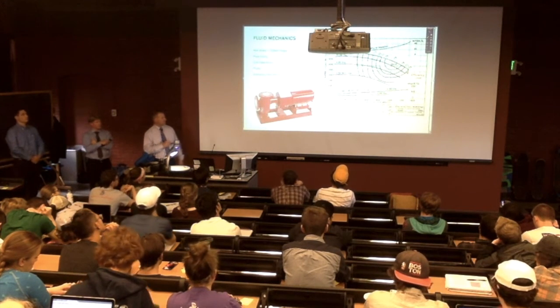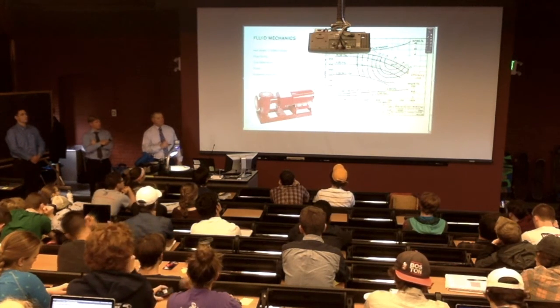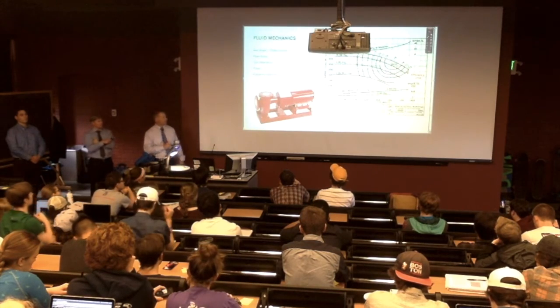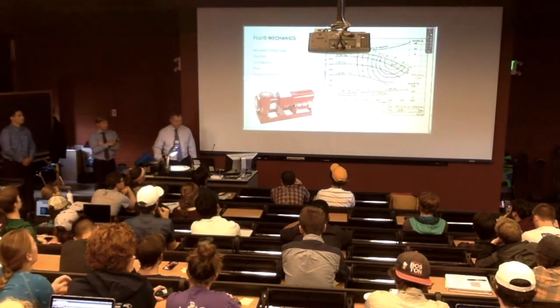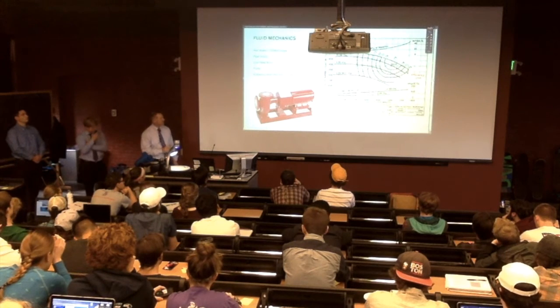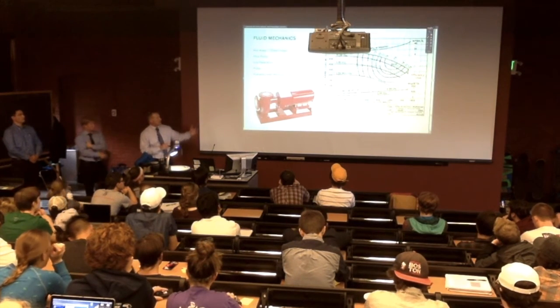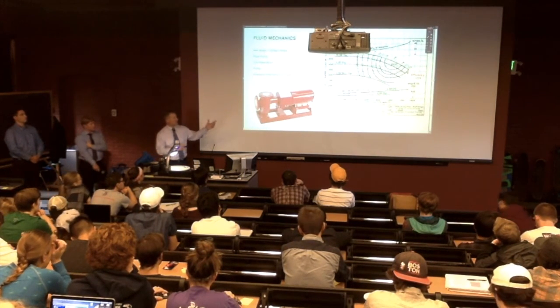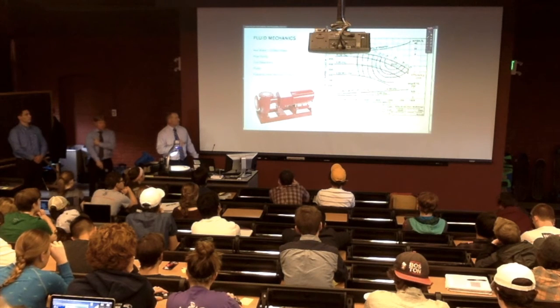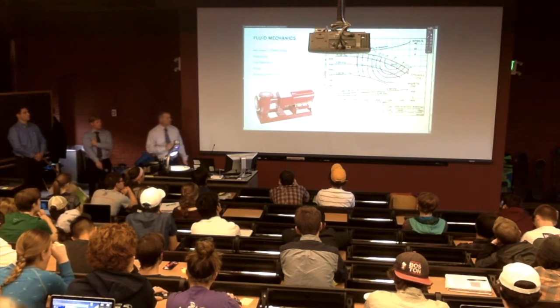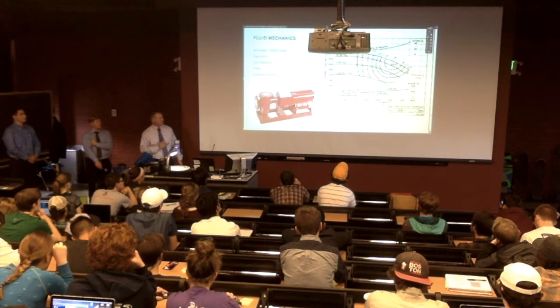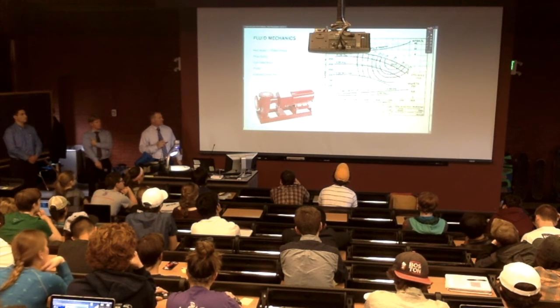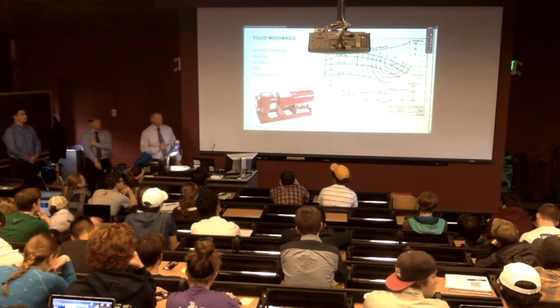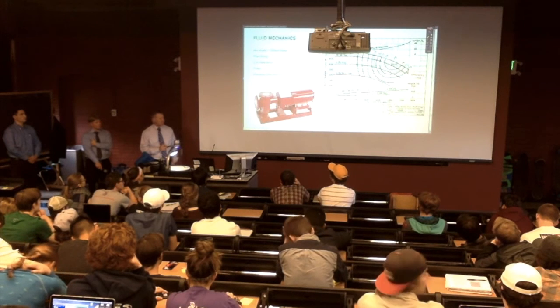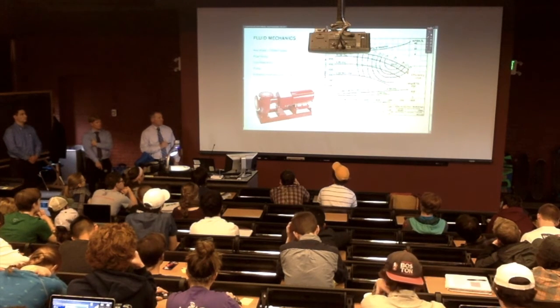This is a manufacturer. That's a Bell & Gossett pump. It's a red pump. Everybody knows a red pump is Bell & Gossett. So other manufacturers out there have different color pumps. But they all have a pump curve with a total dynamic head on the y-axis, the gallons per minute on the x-axis. These are the sizes of the impeller that actually goes inside that pump. And, again, it's something that you have to work your way through in the design of the building.